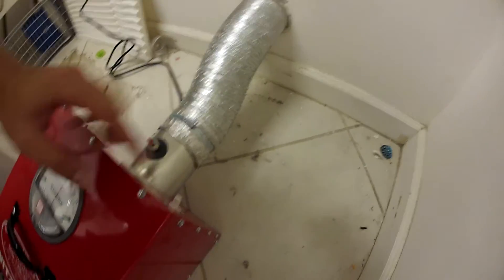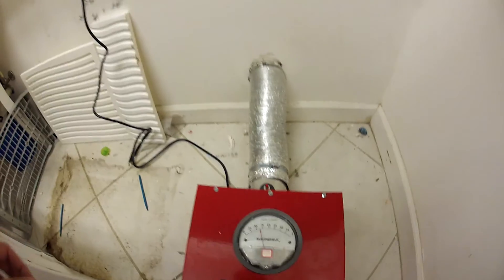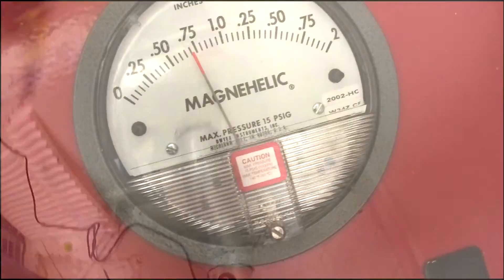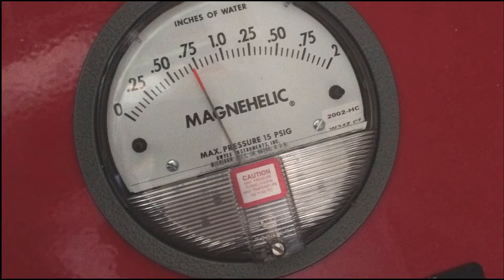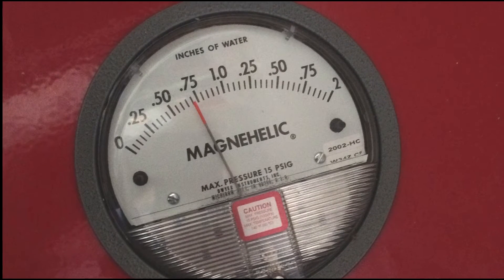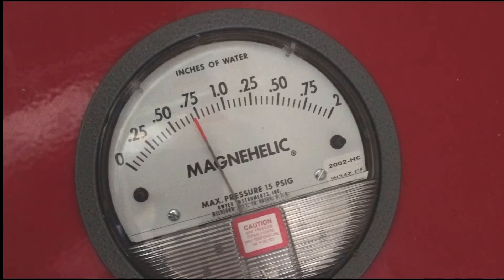Once it's been connected, we can now turn on or activate the actual dryer exhaust blower to generate airflow through the dryer exhaust duct. Once you've activated the device, take a look at the Magnehelic gauge and record the amount of back pressure in that system now that the dryer exhaust duct is clean.